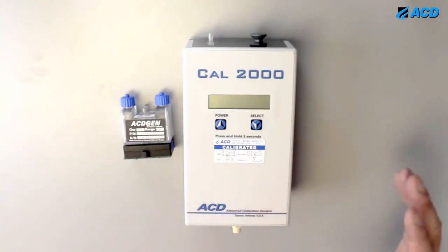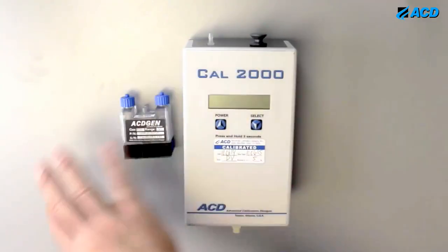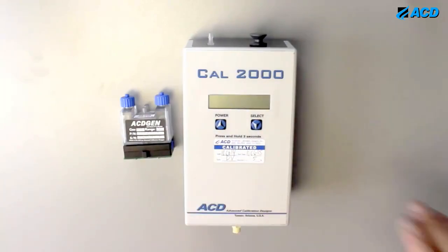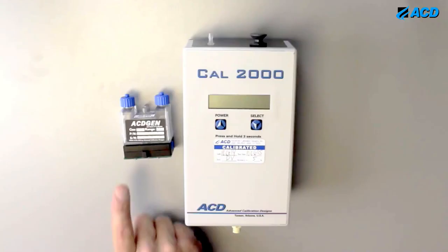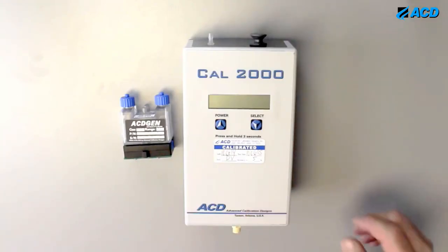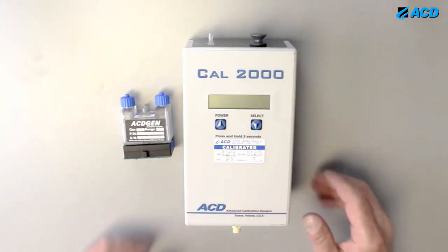We sell different sources, so you can buy one instrument and then buy sources for hydrogen, chlorine, chlorine dioxide, whatever different gases that we sell, and you put the source into the instrument and then calibrate gas detectors with it.